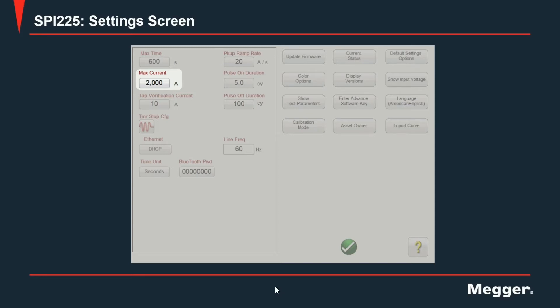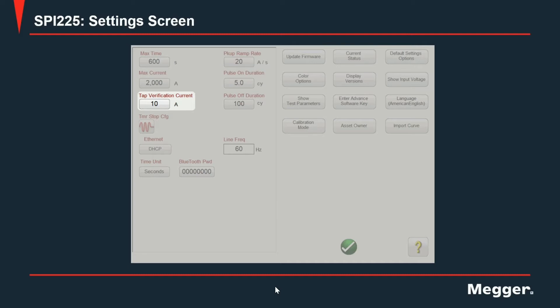Next is tap verification. As you know, the SPI 225 output is electronically controlled. When a user sets the output at a given value, the unit first will have to do a pre-injection to determine the impedance of the circuit connected to the output so the current requested by the user can be adjusted. That first or initial injection that the unit does is done using this current set in the tap verification setting.